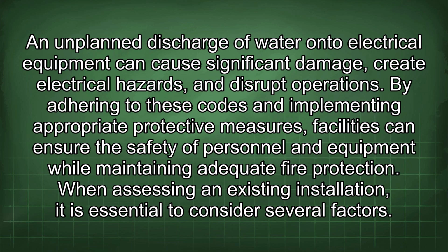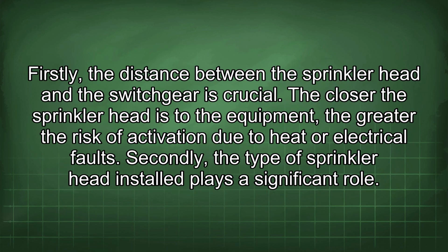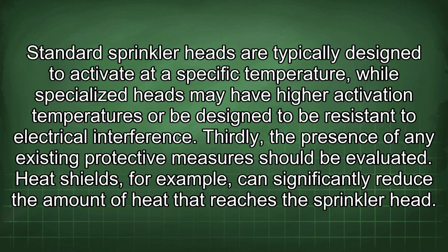By adhering to these codes and implementing appropriate protective measures, facilities can ensure the safety of personnel and equipment while maintaining adequate fire protection. When assessing an existing installation, it is essential to consider several factors. Firstly, the distance between the sprinkler head and the switchgear is crucial. The closer the sprinkler head is to the equipment, the greater the risk of activation due to heat or electrical faults. Secondly, the type of sprinkler head installed plays a significant role. Standard sprinkler heads are typically designed to activate at a specific temperature, while specialized heads may have higher activation temperatures or be designed to be resistant to electrical interference.